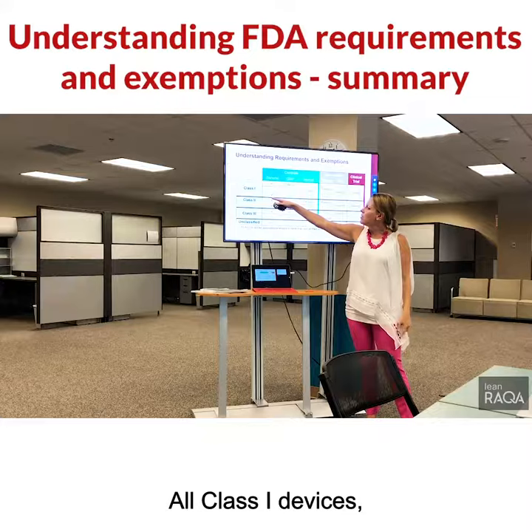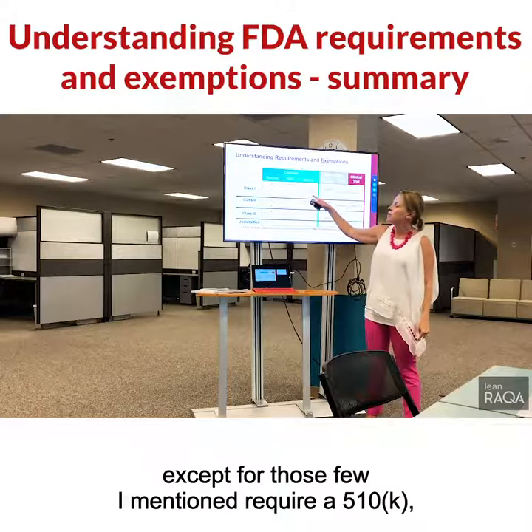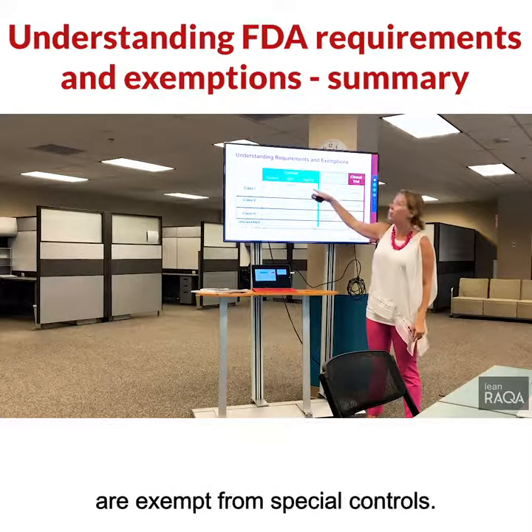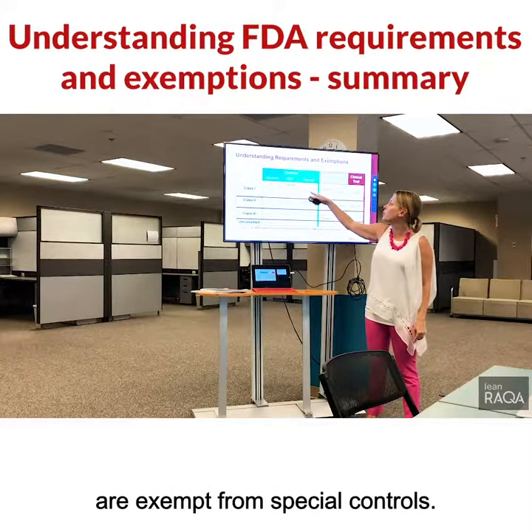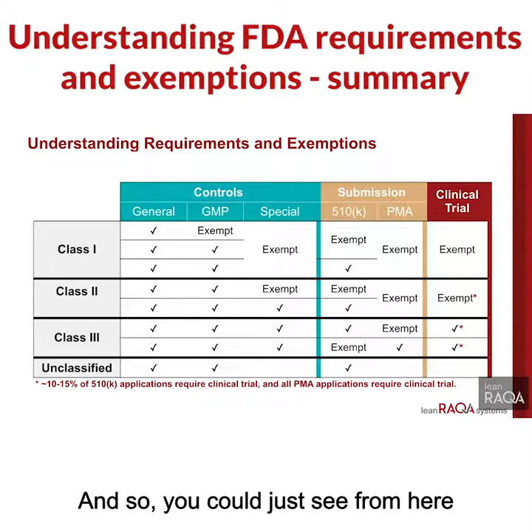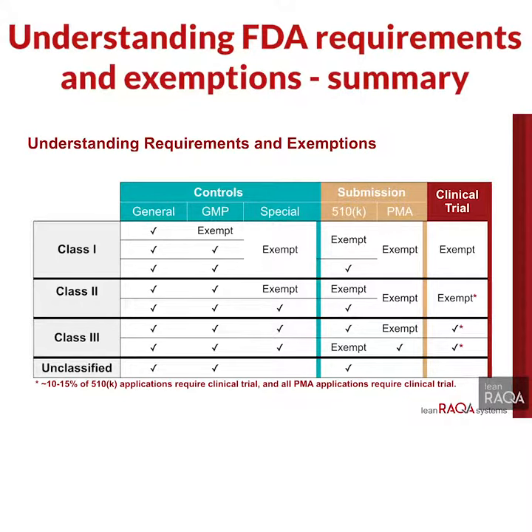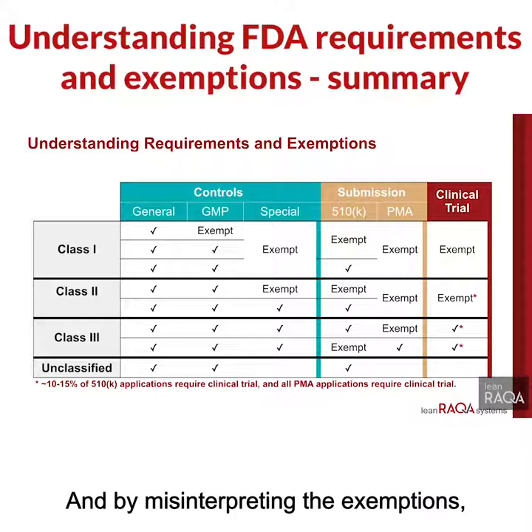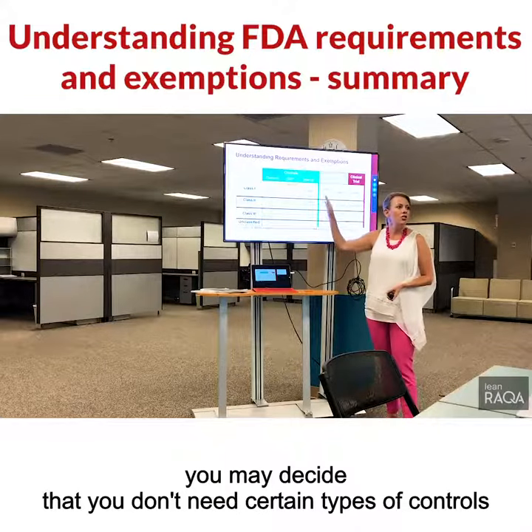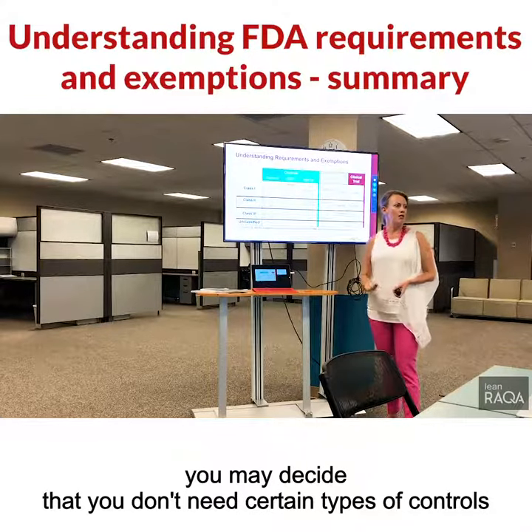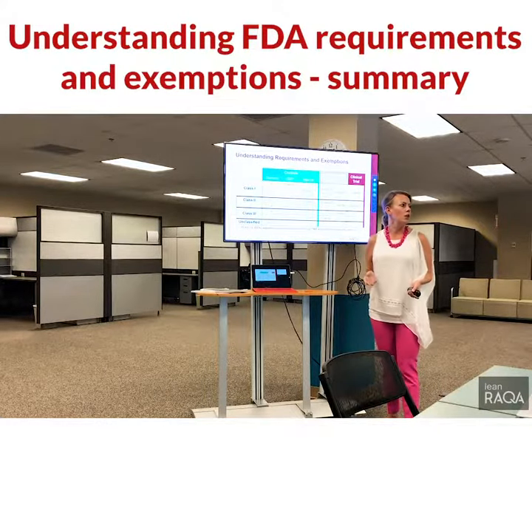All class one devices, except for those few I mentioned that require a 510K, are exempt from special controls. And so you can just see from here how complex it is just to understand the submission and the exemptions. By misinterpreting the exemptions, you may decide that you don't need certain types of controls when you really do.